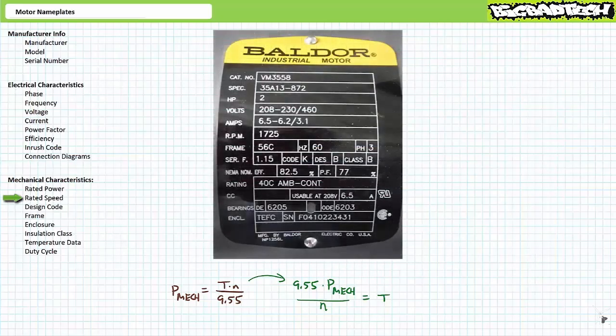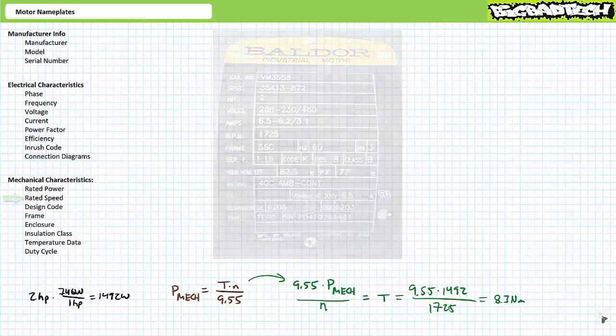Consider the previous 2 horsepower motor with a rated speed of 1725 RPM. A unit conversion demonstrates 2 horsepower is equal to 1,492 watts, or roughly 1.5 kilowatts. Substituting mechanical power in units of watts and rotational speed into our algebraic manipulation demonstrates this motor produces 8.3 Newton meters of torque at the rated condition.